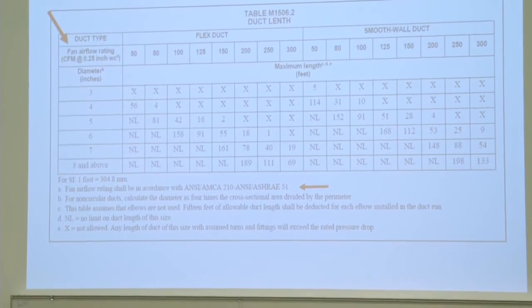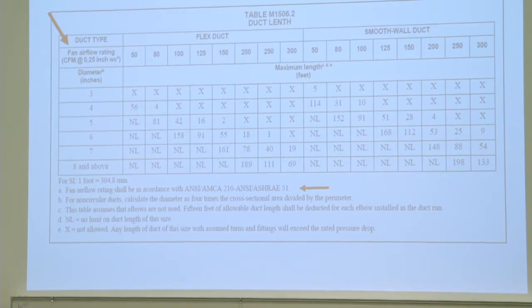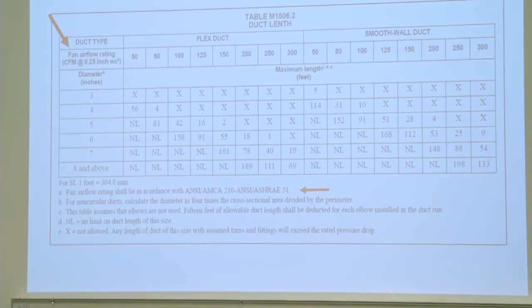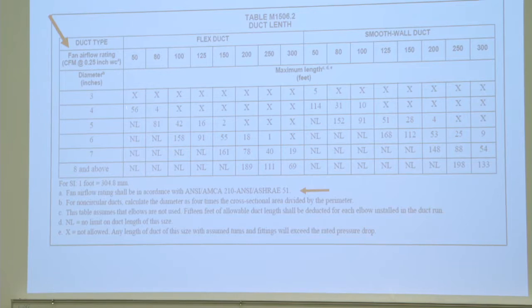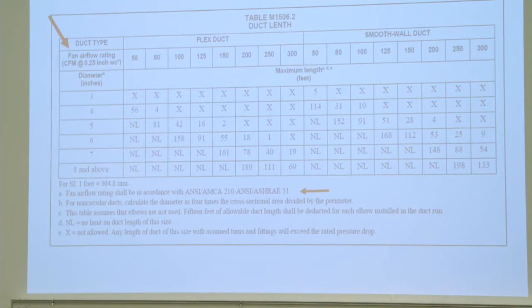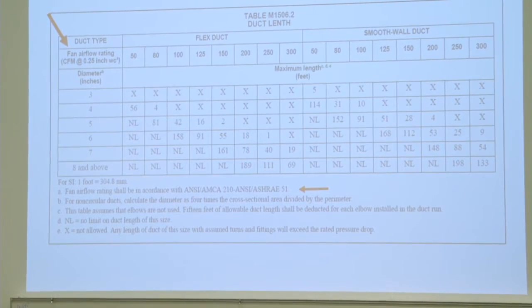An 80 CFM fan, you can only put 4 feet of flex on it. If it says NL, there's no limit. So if you only want to move 50 CFM and you have 5-inch, you can run it 100 feet if you wanted to. This is out of the IRC.